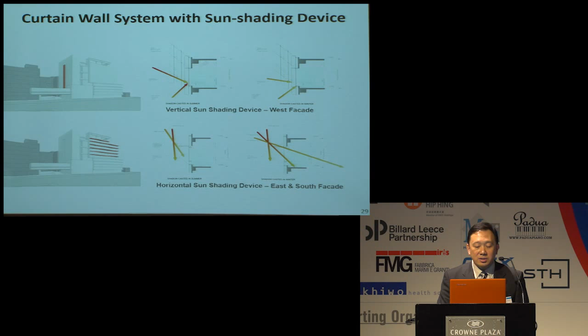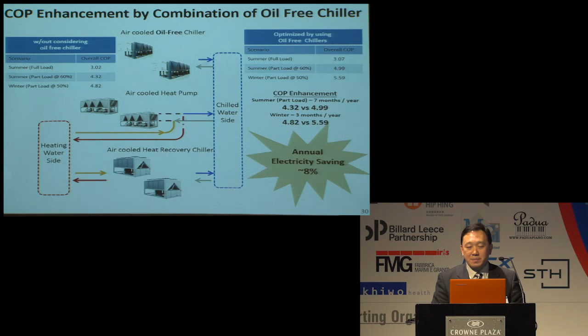That's why we introduced all these sun shading devices, which Victor covered a little bit. We also introduced an oil-free chiller system, which can have a much higher COP, not only at peak load but also at part load. So when the chiller system is operating at full capacity, the efficiency is still very high. We estimated the annual saving will be around 8%.